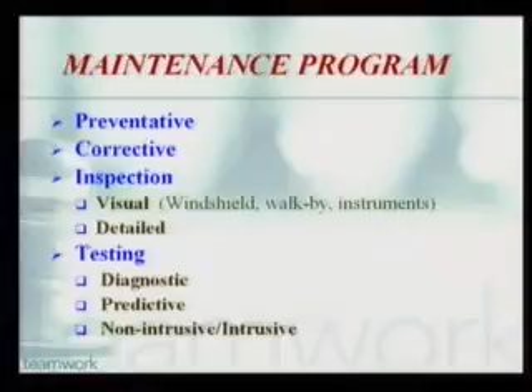There's predictive maintenance, where based on milestones, the number of operations, and based on recommendations by manufacturers, corrections that we can do or inspections we can do on the device. Then there's also what we call non-intrusive and intrusive testing. Non-intrusive testing includes all testing that we do on the transformers, circuit breakers, as well as using infrared cameras. These are things that we don't interrupt service. We actually are performing testing either from a distance or without interrupting service. And then there's intrusive testing. Intrusive testing involves either moving, in case of poles or field devices, actually moving the equipment, taking it out of service, or taking some samples for a more detailed analysis.